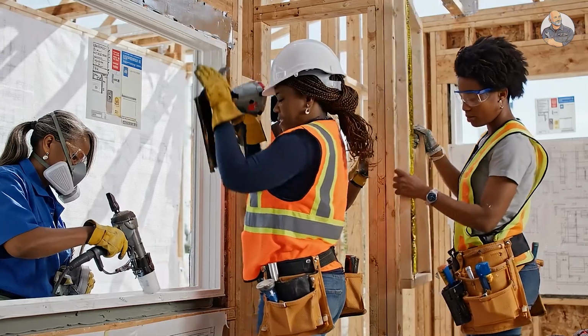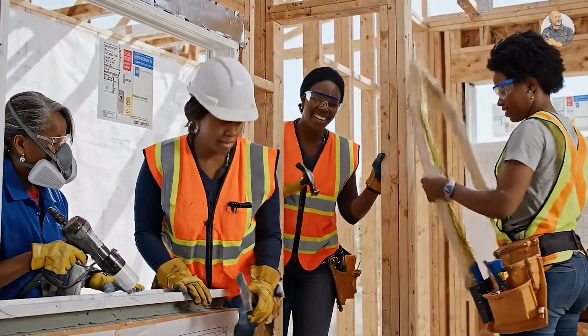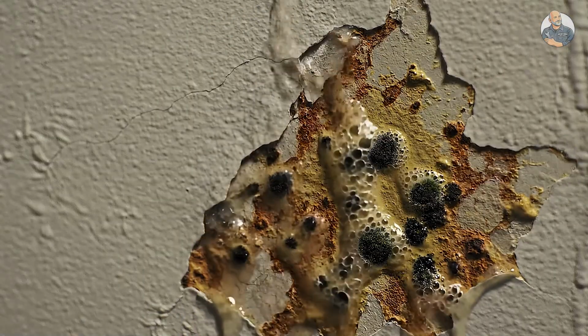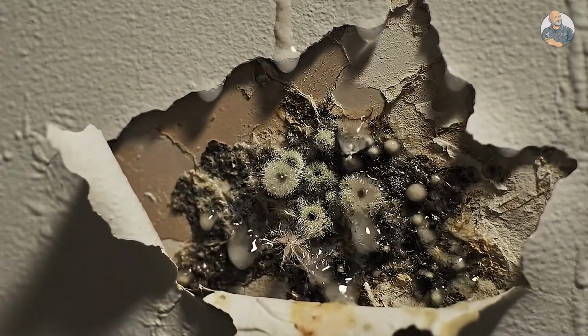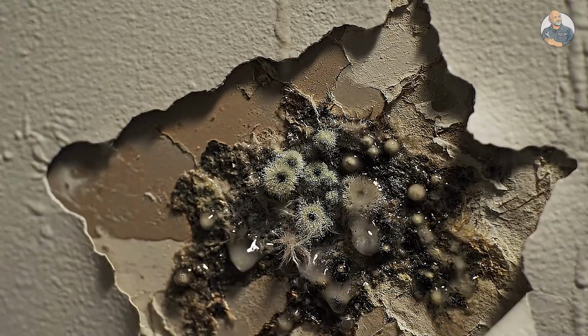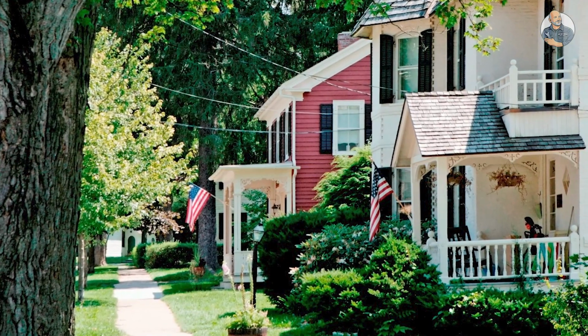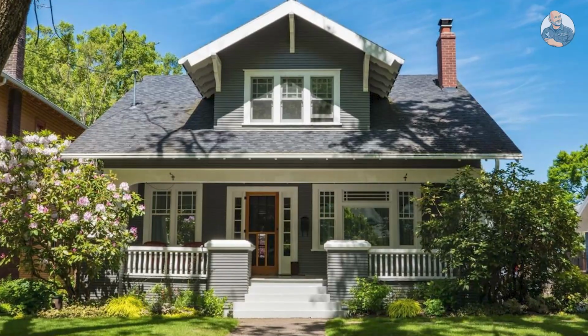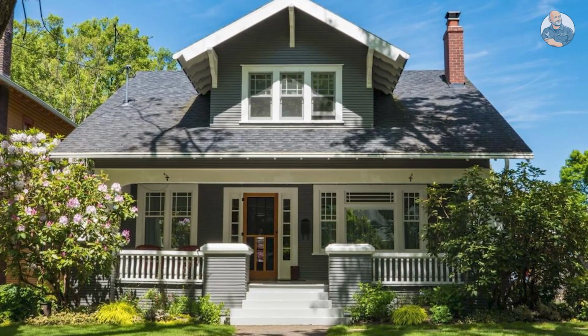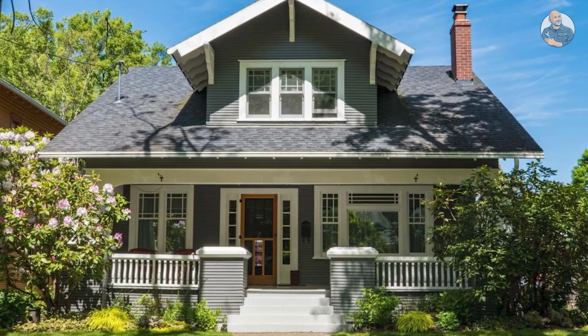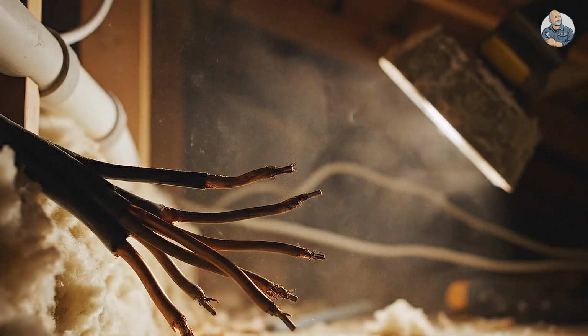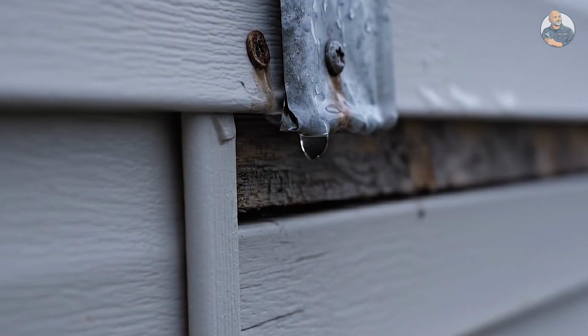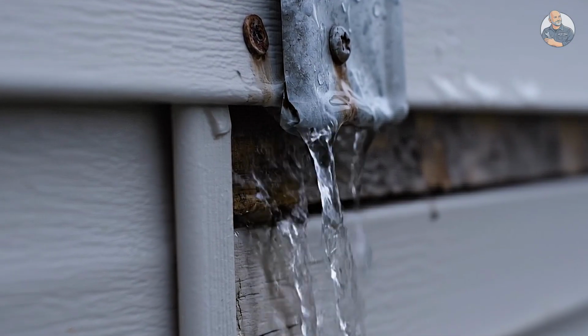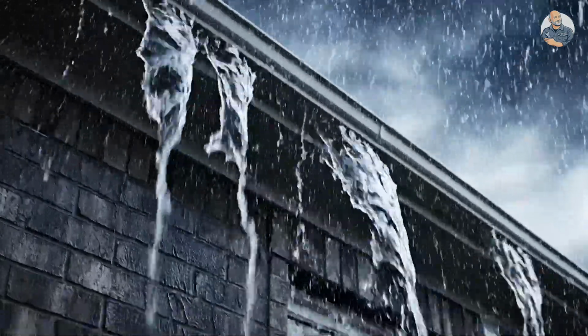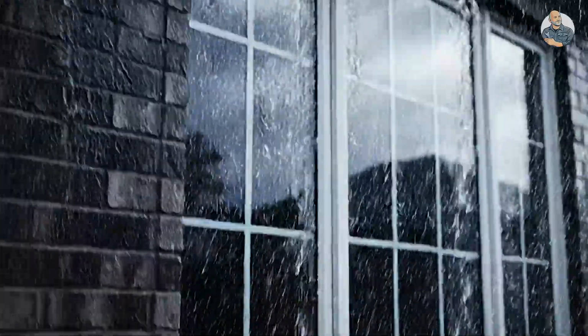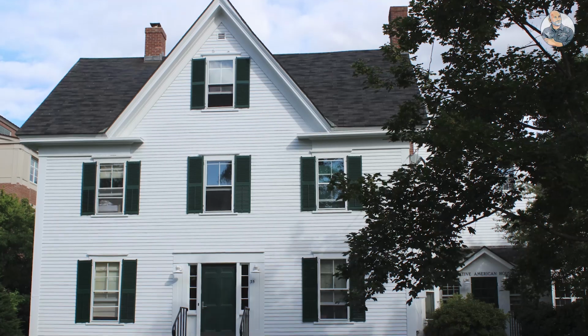Because if something can't be measured, it's really just a promise. A properly documented new home should be able to show proof of basic performance tests. That includes a blower door test that measures how much air leaks through the structure, a duct leakage test that confirms conditioned air isn't escaping into attics or crawl spaces, and HVAC commissioning records that show airflow and pressure were actually measured when the system was installed. Programs like Energy Star even publish commissioning checklists specifically for this reason, to confirm that the system works the way it was designed, not just that it turns on.